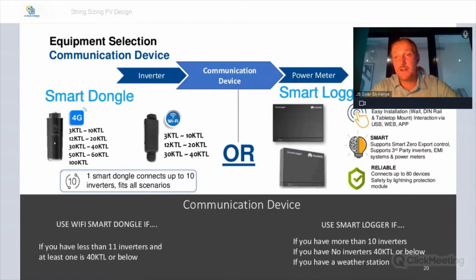Okay, so after you've identified your inverter, you have to identify your communication device, because this is what allows you to monitor remotely. So on the screen, I have the big OR in the middle, because you can either use a smart dongle on the left or a smart logger on the right. You do not need both. You choose one. So at the bottom in the gray area with the white text, I've tried to make it clear. Let's look at the smart dongles on the left first. There's two models: the 4G model and the Wi-Fi model. The 4G model requires a SIM card and you have to keep uploading data. So I personally prefer the Wi-Fi model and I recommend using it whenever possible.